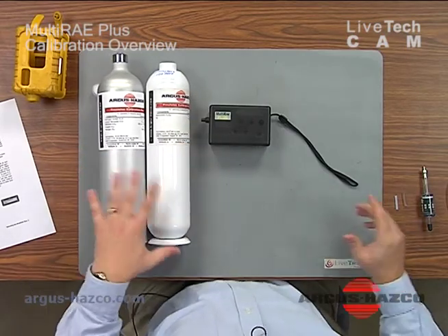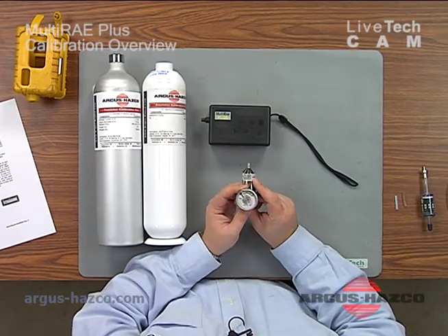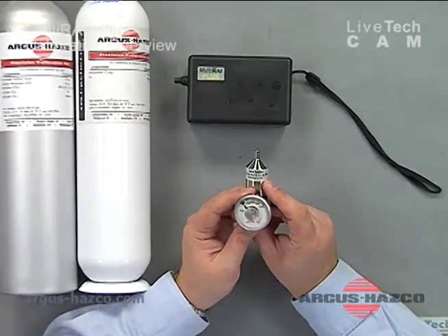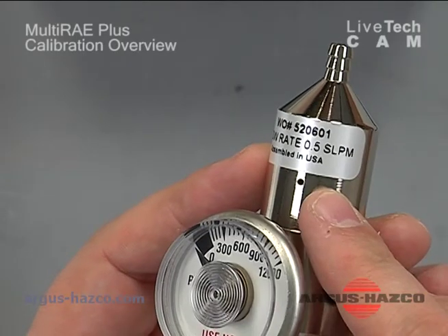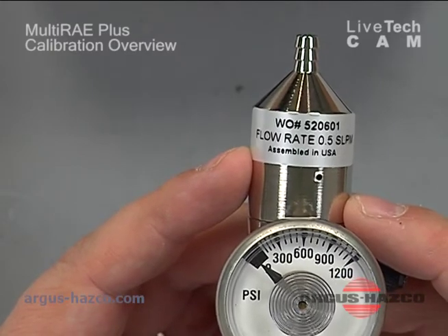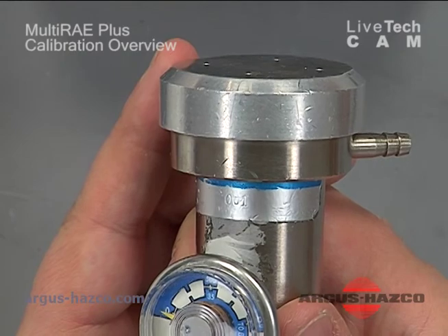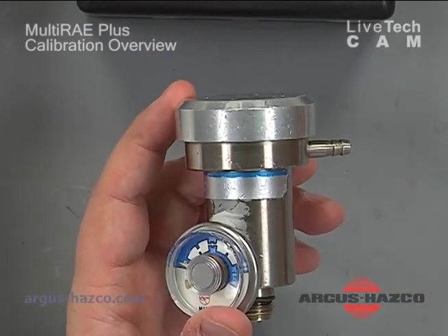At this point you have two options that RAE Systems offers. You have a 0.5 liter per minute flow regulator, indicated on a sticker on your regulator. The flow rate of 0.5 L/min matches the flow of their internal pump. Or you have a demand flow regulator, which will only open and flow based upon what is demanded by the pump — it basically matches the pump flow. That is what is recommended if available.